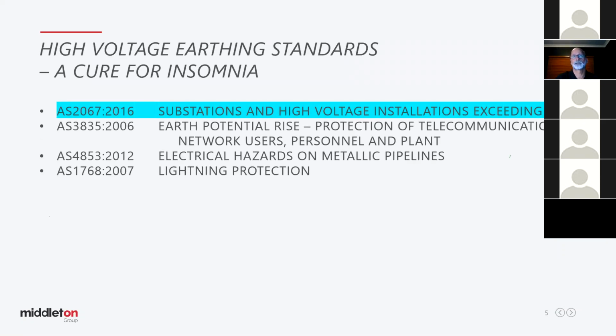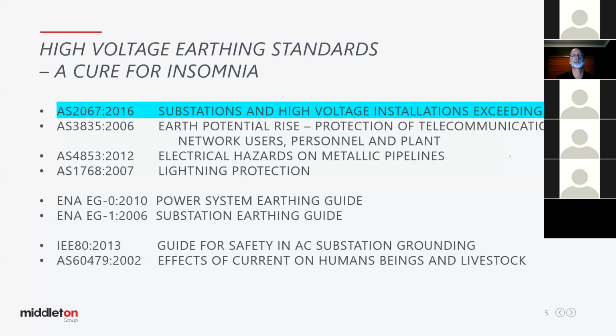Talking about standards, and we won't talk about them for long because they're a good cure for insomnia. AS2067 is a very common earthing standard to be used nowadays. It's backed up by a few other standards that are common to use. So we're not only looking at the voltages around substations, but also on our telecommunications equipment that can transfer voltages. We're also looking at metallic pipelines. There's plenty of pipelines around electrical assets that are conductive and can transfer dangerous voltages. So those references are in there too.